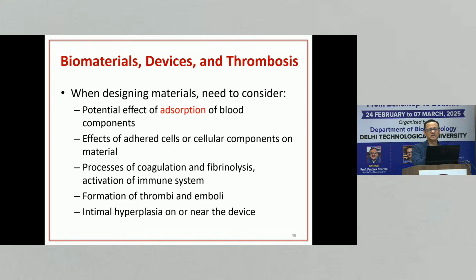Is your material going to be toxic? So if you put a coating on your catheter, it's going to go in your blood vessel. Is that going to leach something, or when it's touching your tissue, is it going to kill any healthy cells? So we need to think about cytotoxicity, we need to think about hemolysis, and while doing all that, its main purpose is it should prevent clotting also.